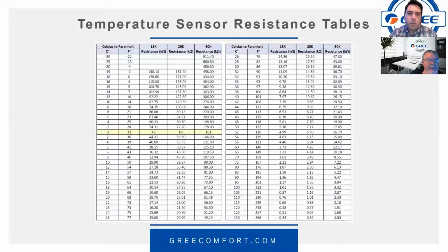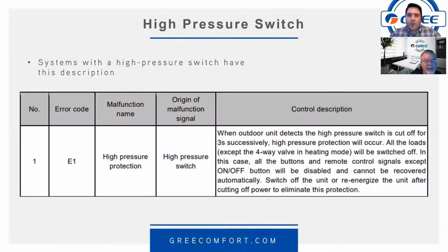So the sensor tables, this is what we put out there. This has both Celsius and Fahrenheit, and that conversion table can come in handy for some of the other tools that we have if you're using a debugger, which we're going to cover in a minute. We've got Celsius, Fahrenheit, all the resistance values for 15K, 20K, and 50K all sitting side by side, and it covers the full range of temperatures for the equipment. And I just have to say, Keith, that's an excellent table that you've built there. Can you explain the highlighted portion of it? That comes up in our tips and tricks. Okay, gotcha.